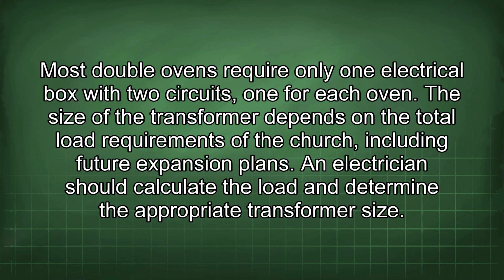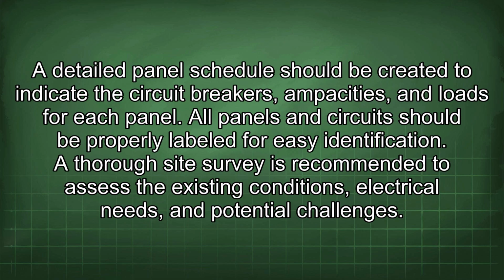The size of the transformer depends on the total load requirements of the church, including future expansion plans. An electrician should calculate the load and determine the appropriate transformer size. A detailed panel schedule should be created to indicate the circuit breakers, ampacities, and loads for each panel. All panels and circuits should be properly labeled for easy identification. A thorough site survey is recommended to assess the existing conditions, electrical needs, and potential challenges.